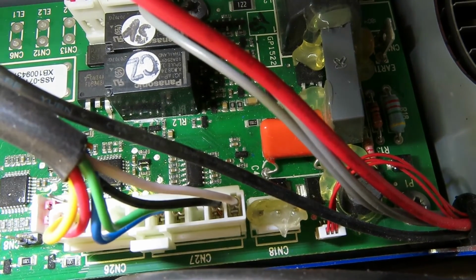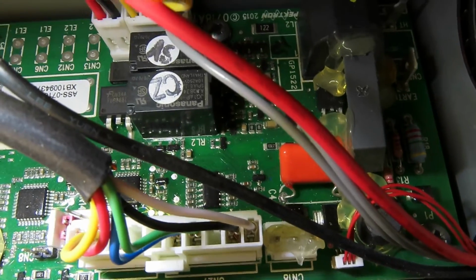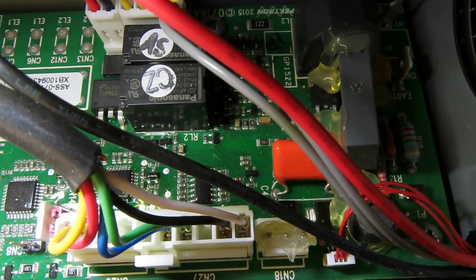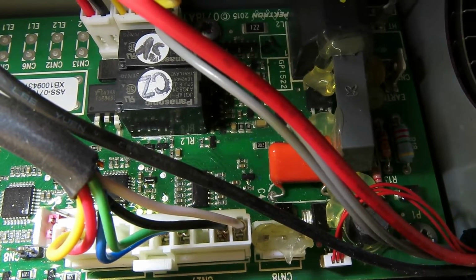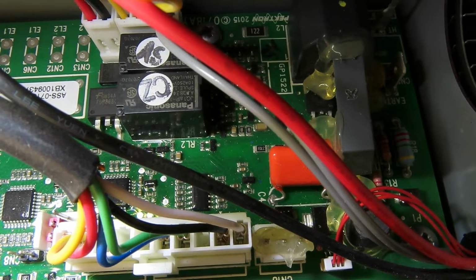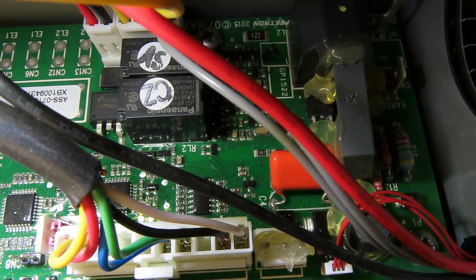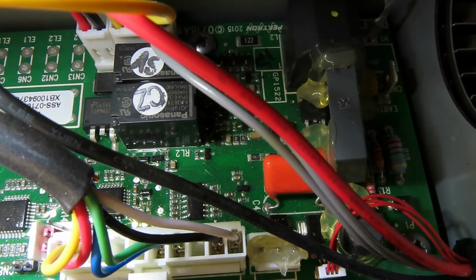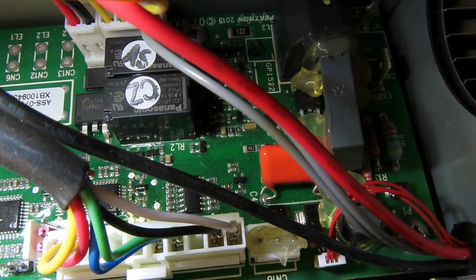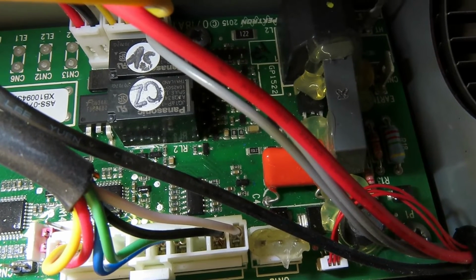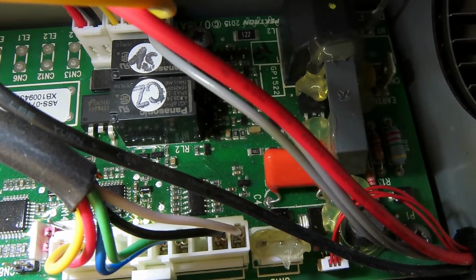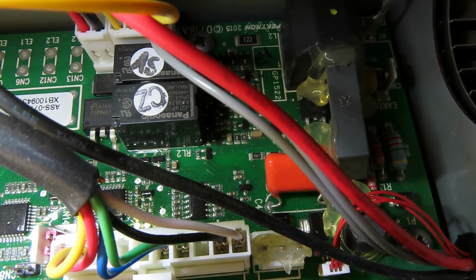Turn the heater on. You have to have the heater on, even though it won't be running, the light will be blinking. Some codes you can only clear this way. Run a paper clip across those left 2 connectors, jumper them, and it will clear the error code. Then you have to do the on-off sequence again, but it will clear the code.